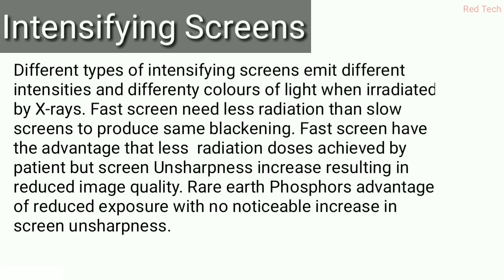Next is the intensifying screen. Different types of intensifying screens emit different intensities and colors of light when exposed to x-rays. Fast screens need less radiation than slow screens to produce the same degree of blackening. Fast screens have the advantage of requiring a lower radiation dose to the patient, but screen unsharpness may increase, reducing image quality.